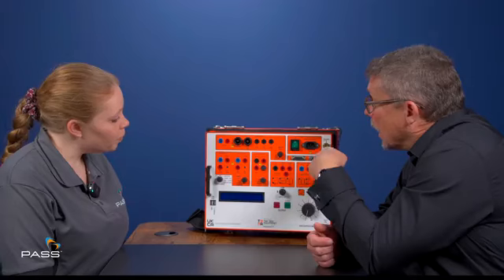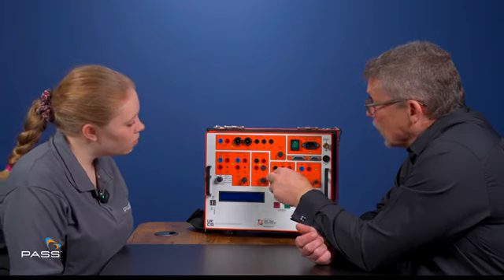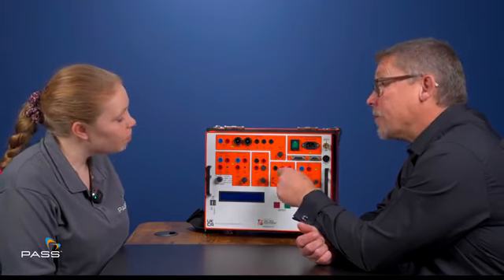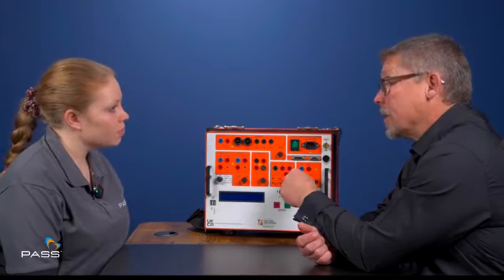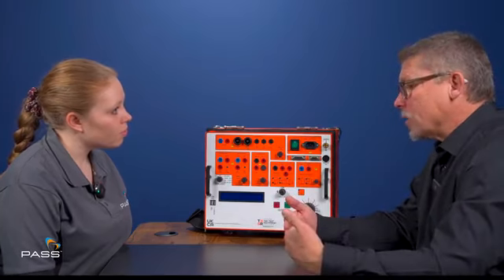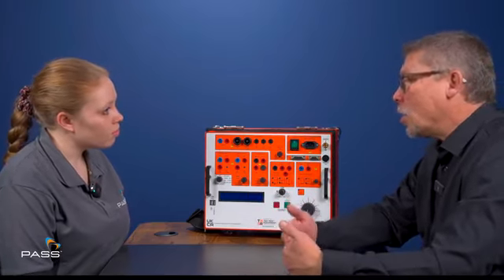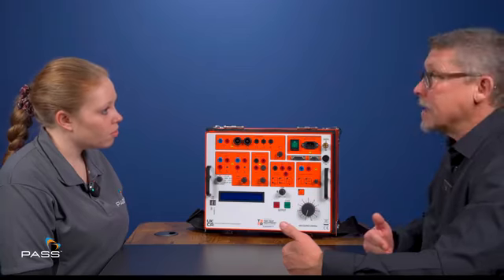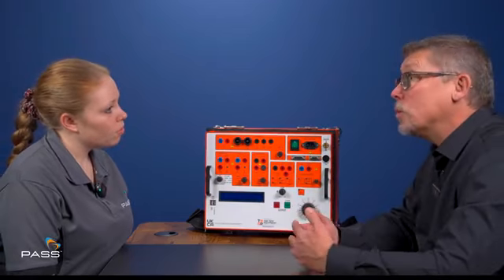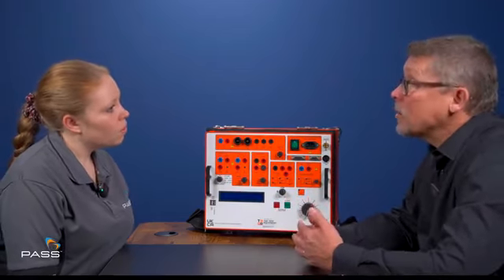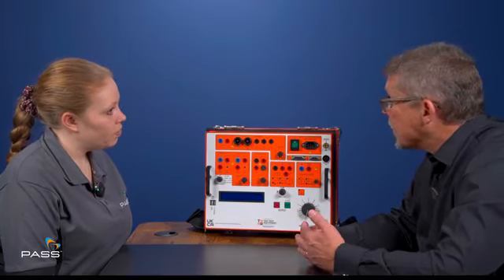In that auxiliary channel, though, we can control the phase angle. So we can shift the phases between these 2 channels. We can also play with the frequency from 45 through to 100 hertz. So what that means is when we're looking at relays, it's adding a whole plethora of extra relays that we can test with this that we wouldn't with a normal run-of-the-mill secondary current injection test set.